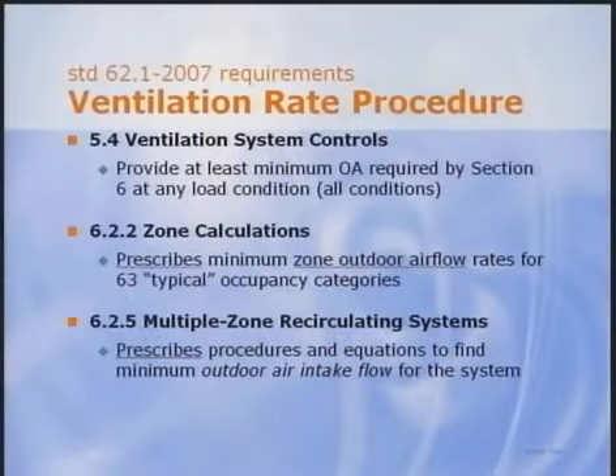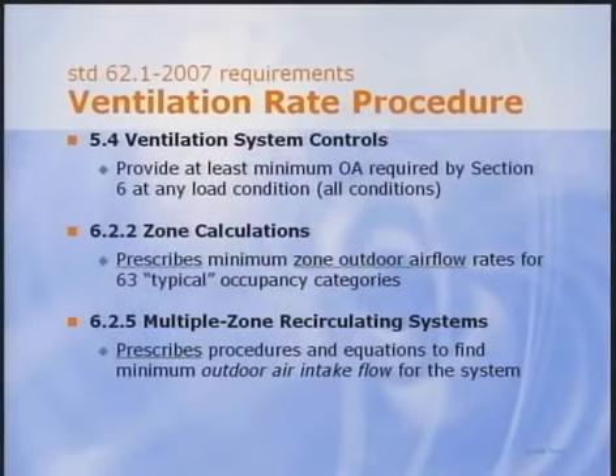Three sections apply. Section 5.4 requires that the system receive no less than the minimum required outdoor airflow at any load condition. Since mixing box pressure at the air handler changes as supply airflow changes, VAV systems should use an outdoor airflow sensor and modulating outdoor and return air dampers to comply with this requirement. Section 6.2.2 prescribes minimum breathing zone outdoor airflow rates for a long list of occupancy categories and a procedure to determine minimum zone outdoor airflow, especially at design. Section 6.2.5, along with Appendix A, prescribes equations to be used to find the intake airflow for any multiple zone recirculating system. These equations must be followed for design, but they also apply at part load. Remember, intake airflow must be sufficient for current ventilation needs at all load conditions.